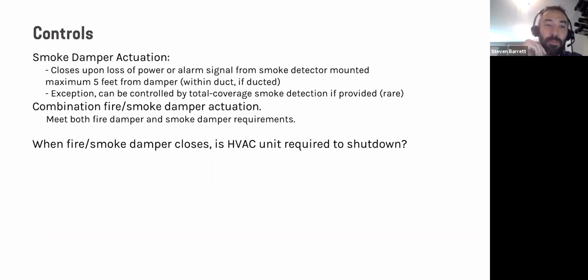So just real quickly, we kind of went over this at the beginning, but how does the smoke damper work? Either on loss of power or an alarm signal from the smoke detector mounted 5 feet from the damper, typically within the duct, but you may have an air transfer opening, so it could be just near the opening within 5 feet. Those are required, a smoke detector somewhere within 5 feet to actuate to close the damper. An exception, which is a bit rare, is if your building has total coverage smoke detection, then you can utilize that system to activate and close the smoke damper. And then if you have the combination fire and smoke damper, then you follow both requirements for fire dampers and for smoke dampers.